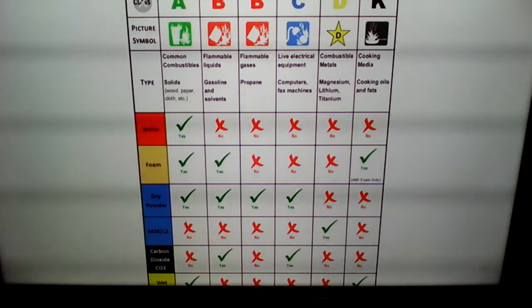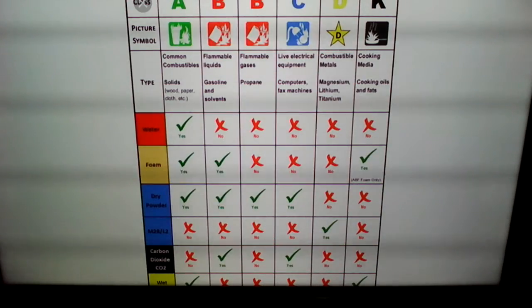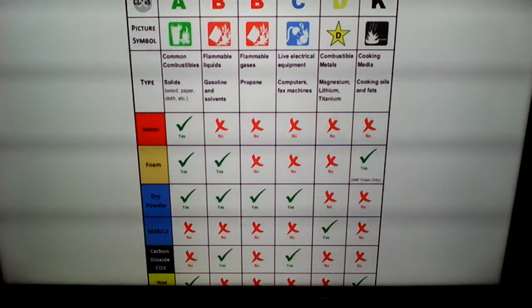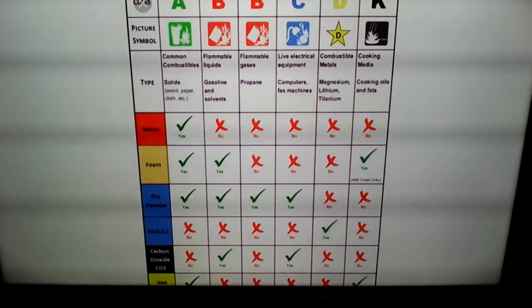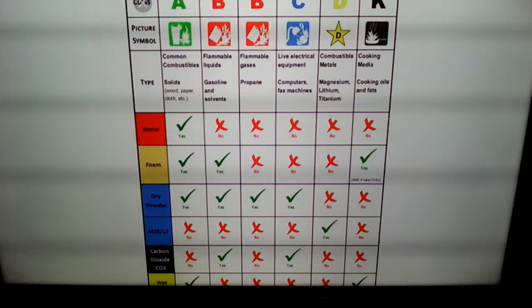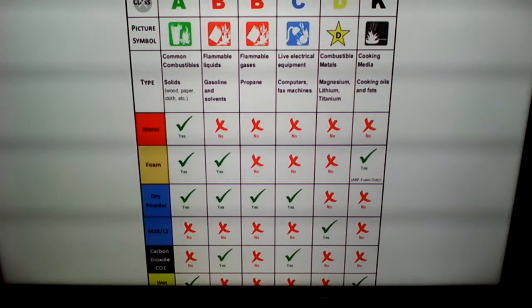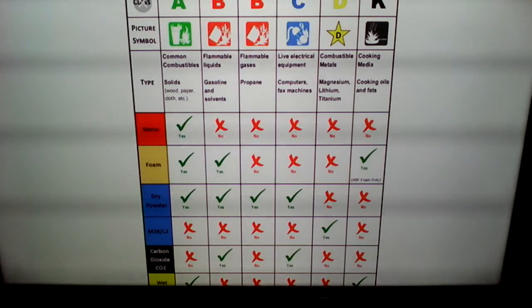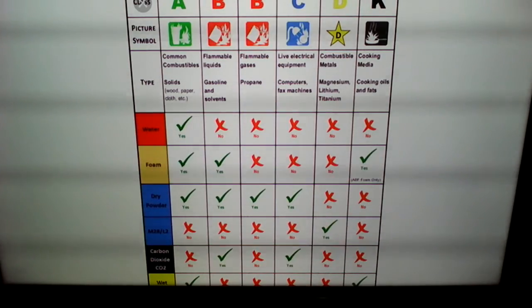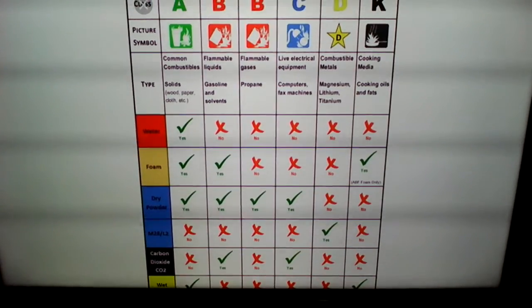They carry a numeric rating that indicates how large a fire an experienced person can safely put out with that extinguisher. Class B extinguishers are used on flammable liquids or gases. Their agents include foam, carbon dioxide, ordinary dry chemicals, and multi-purpose dry chemicals. Similar to Class A extinguishers, numerical ratings indicate how large a fire an experienced person can put out.